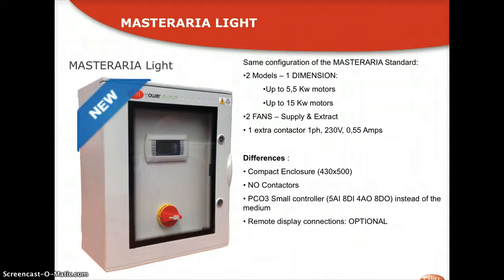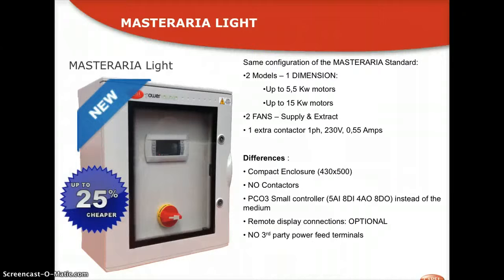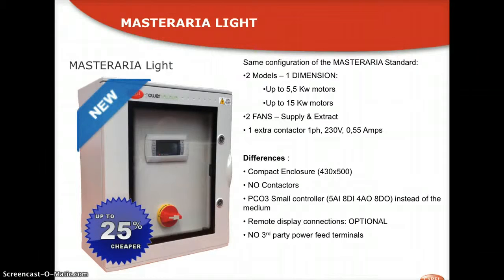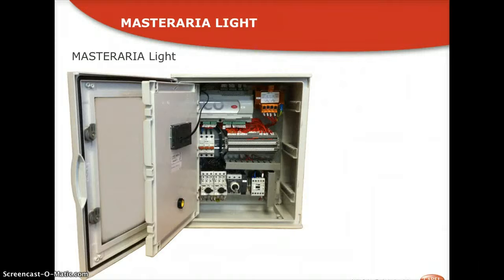The remote display connection, the T-Con splitter, to connect a remote display is optional and does not have a third-party power feed terminals for what we were saying earlier on for humidifiers and condensing units. The great thing of this panel is that it is very cost aggressive, and it is about 25% cheaper than the Masteraria Standard. It is a double door panel, like you see here.